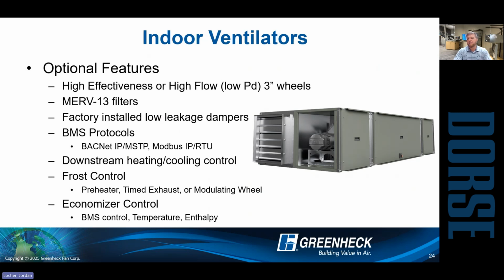Some of the optional features: we standardized on using a 3-inch thick wheel to maximize that recovery. There is a difference in either a high effectiveness or high flow wheel, depending on the airflow that you're looking at. We can do up to MERV 13 filters. We have factory installed dampers, all the different BMS protocols. You can control downstream heating or cooling, so if you did want to pair this with some sort of split coil. And then we have built-in factory frost control and economizer sequences. Whether it's a preheater or being a wheel unit, that modulating wheel is a really awesome option for both economizing and frost control. You can actually slow down the speed of the wheel and gain a lot of benefits that way. So very, very powerful. A lot of different factory sequences are included with these units.